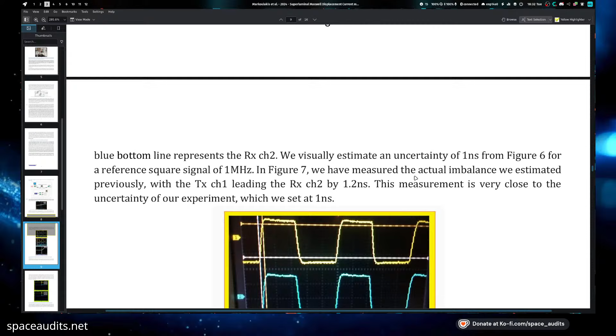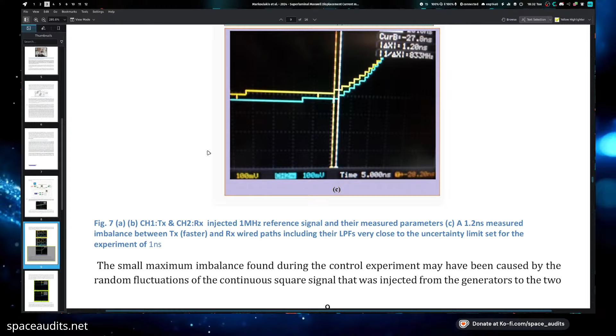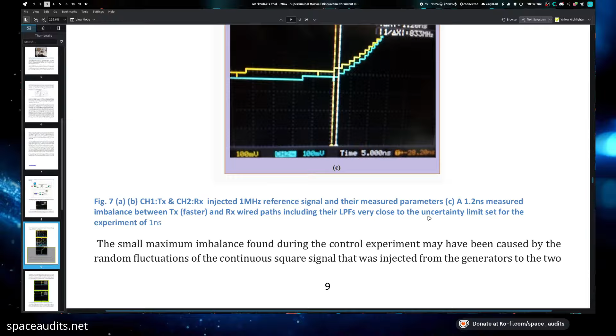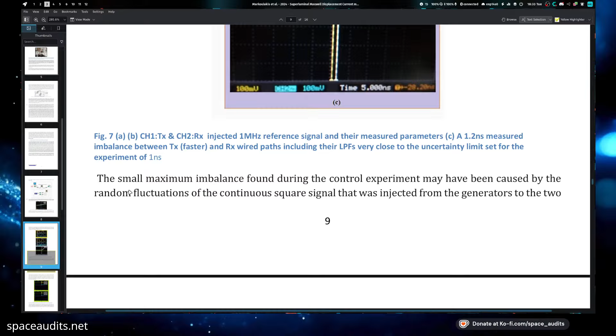Okay. So we got some nicely synchronized 1 megahertz blocks between transmitter and receiver. All right, Figure 7, A and B, channel 1 transmitter and channel 2 receiver injected 1 megahertz reference signals and their measured parameters in C. A 1.2 nanoseconds is the measured imbalance between the transmitter and the receiver wire paths, including their low pass filters, very close to the uncertainty limit, which was set for the experiment at 1 nanosecond. All right, would you like to take over? Yeah, I think we could do that.